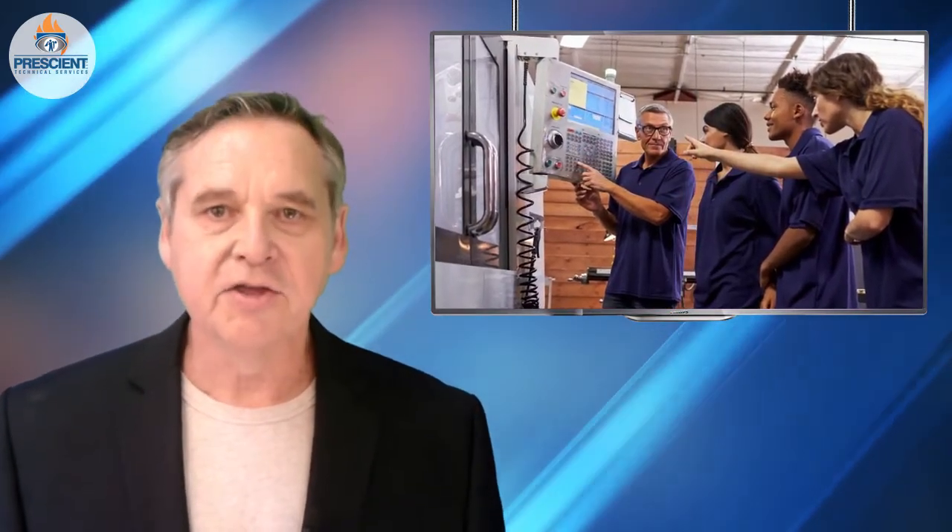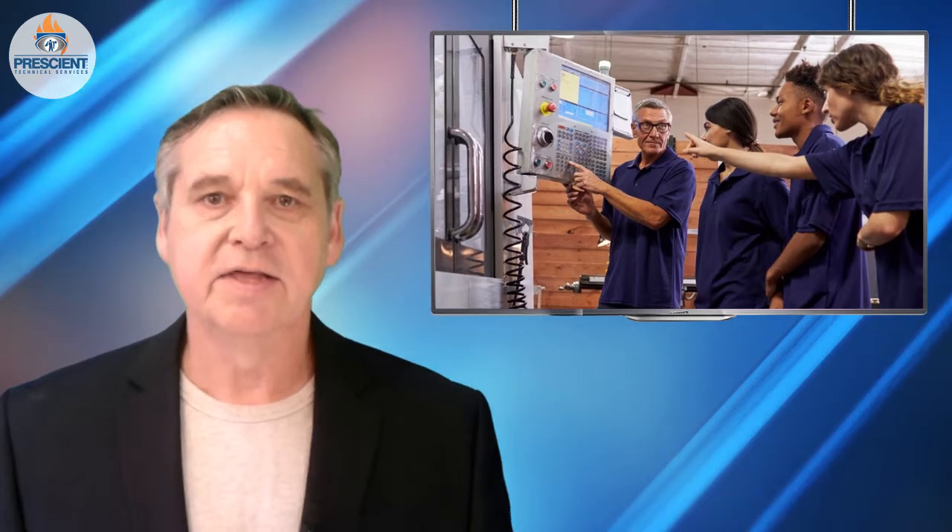So what are some of the things that might be in a pre-start walk-down checklist? Well, first of all, let's start with the proper PPE — personal protective equipment. Should you have gloves on? Should you have FR clothing, fire-resistant clothing? Should you have safety glasses? What about the footwear you're using? What about basic communications between you and other shifts and maintenance folks? Did the equipment run properly the last time it performed? Was there maintenance performed recently, and if so, why? What were the operational problems that existed? What should you be on the lookout for when operating this equipment?